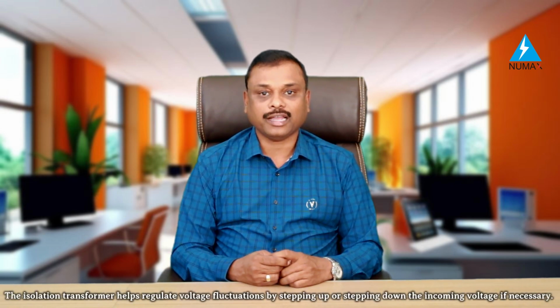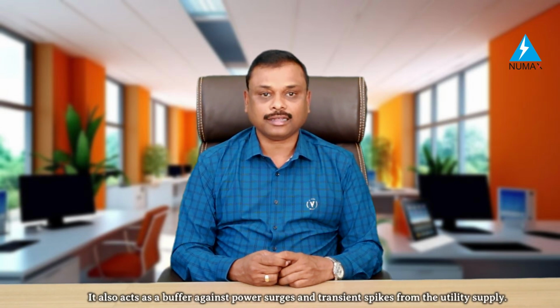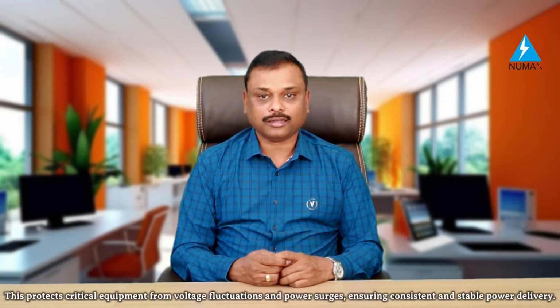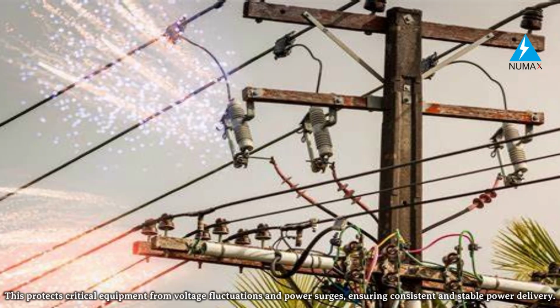The isolation transformer helps regulate voltage fluctuations by stepping up or stepping down the incoming voltage, if necessary. It also acts as a buffer against power surges and transient spikes from the utility supply. Benefit: this protects critical equipment from voltage fluctuation and power surge, ensuring consistent and stable power supply delivery.